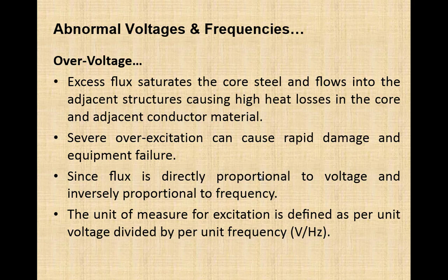If the machine is operating at a rated voltage at rated frequency, it will produce rated flux inside the stator core. Now the excitation, the flux in the core, is proportional to voltage and inversely proportional to the frequency. It means either an increase in voltage or a decrease in frequency. Both these situations will result in an increase in flux, known as overexcitation.